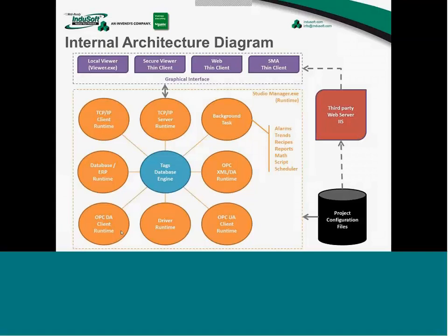And what happens is each one of those tasks is responsible for one specific functionality, and they exchange data with the tags database by exception, so only when tags change values. For example, the driver runtime. If you configure native drivers for communication in InduSoft Web Studio, each driver will be communicating with the PLCs or IOs, whatever it's configured to communicate with. And when it receives a new value, and only when it receives a new value, if one tag changes value or quality or timestamp, then the driver runtime sends the updated information to the tags database. And it's done. It's unaware of the other tasks.